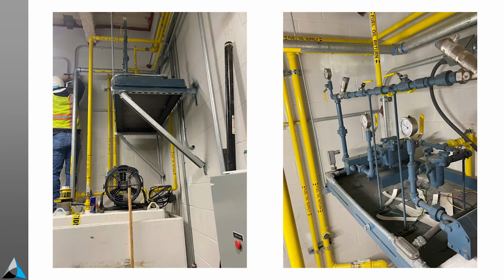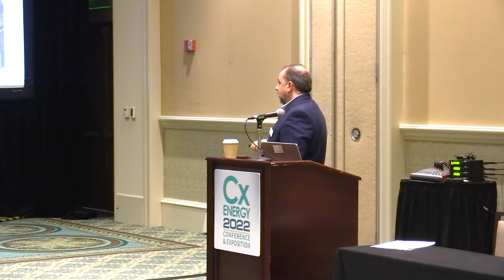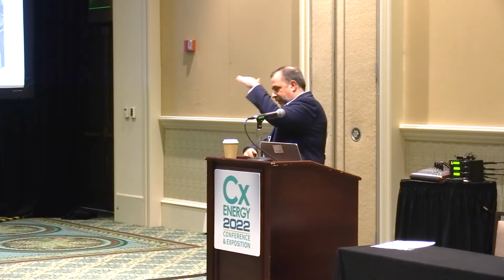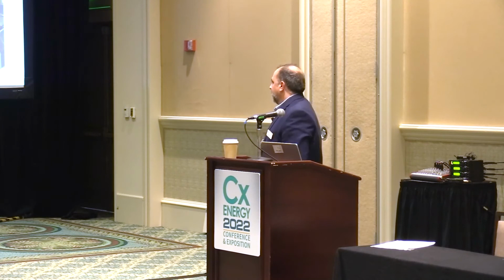Here's another tight generator room where the day tank is shown on the drawings. We never did get the submittals, but the design intent was that the return pumps were integral with the day tank, usually mounted on top of it. Apparently when the return pumps and day tank showed up, they weren't integral after all.